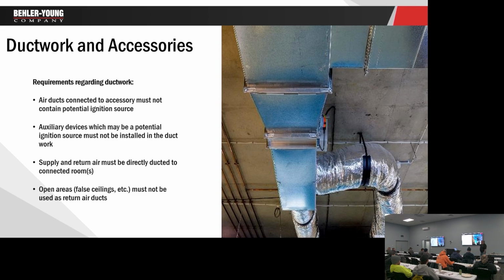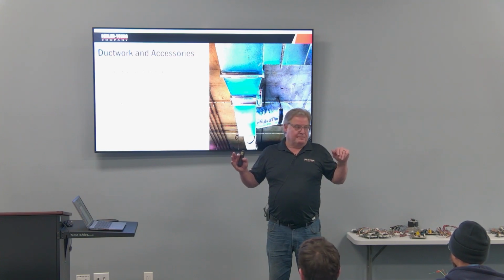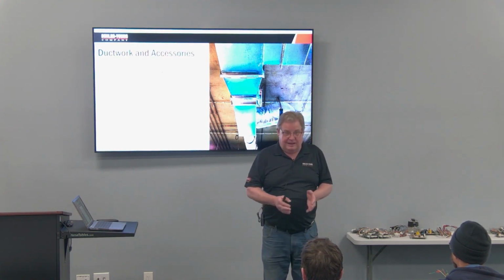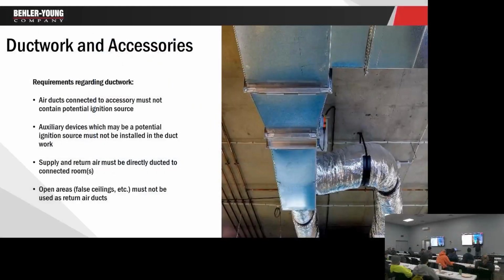Again, I don't want to go too in depth on this on R-32 or 454B, but there are some new rules. 4 years ago, we couldn't use an A2L refrigerant because the building code wouldn't allow it. So the BOCA code was rewritten to accommodate it, and all 50 states accepted it. Michigan accepted it last spring. However, if you call your local inspector right now, has anybody talked to their inspector about 454B yet? Most of them are going to scratch their heads and look at you. They don't even know how the state code is changing yet. So I'm giving you the information I have right now, but it's going to be up to you guys. You're going to have to get with your inspectors as they start to figure this out, what's going to be required.